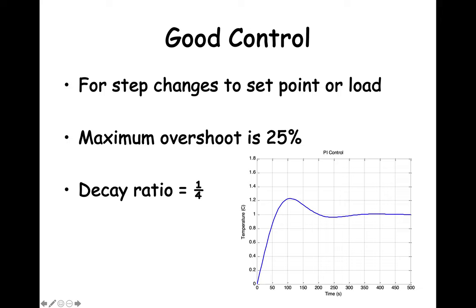Here are the definitions of good control we will use in this class when setting the values of Kp, tau i, and tau d. In general, most process operators want the response to a step change in either the setpoint or a variable process input to produce a maximum overshoot within 25 percent. The other good control performance response is that the decay ratio is one quarter or less, again in response to a step change in one of the inputs. There are other process control indicators, but they are beyond what we have time for in this class. We may also run into cases where the user will set other performance criteria, but the maximum overshoot and decay ratios are the most common criteria.